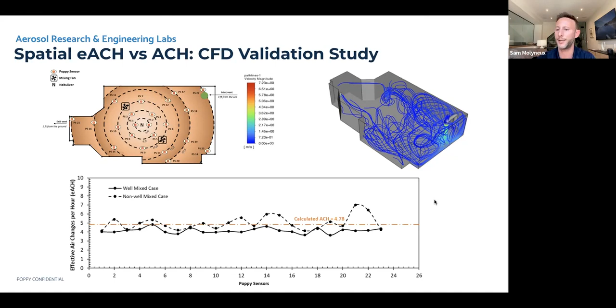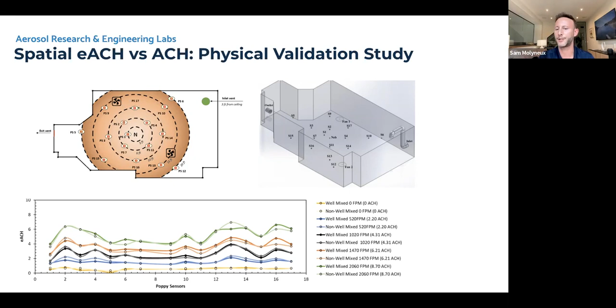We then replicated this in physical space, building another chamber very similar to the virtual one. We saw exactly the same thing at a variety of induced air change rates. We added fans to create mixing and non-mixed conditions, and what we saw is that EACH is fundamentally different than ACH. ACH is a proxy of the particle removal rates in the breathing zone at the floor, where people would interact in this office space. It's clear that measuring the particle removal rate directly is the thing you want to do.